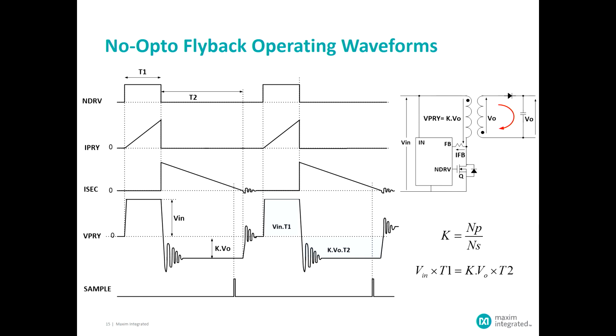That gives us a measure of what the output voltage is. We can compare that to a reference and decide what correction action needs to be taken, and make that correction in time for the next switching pulse - changing the pulse width to get more or less current depending on whether we want to raise or lower the voltage. That lets us close the regulation loop entirely on the primary side.